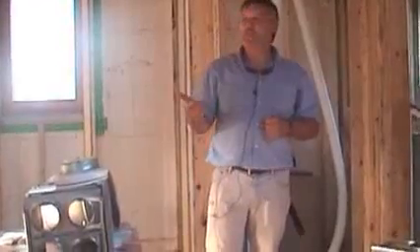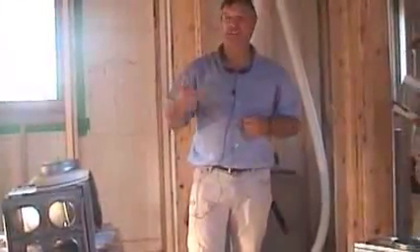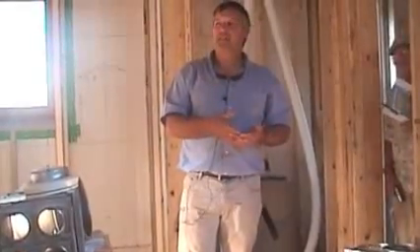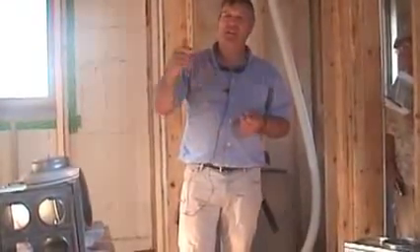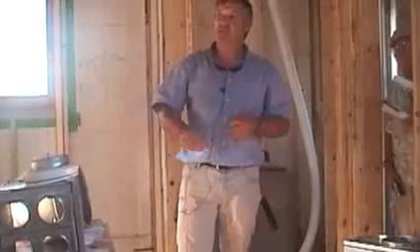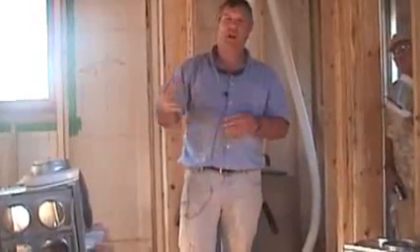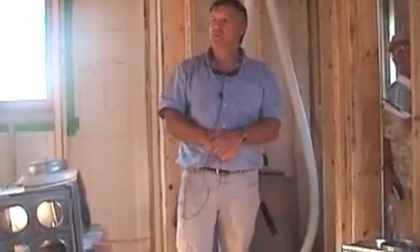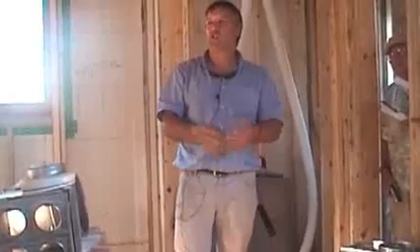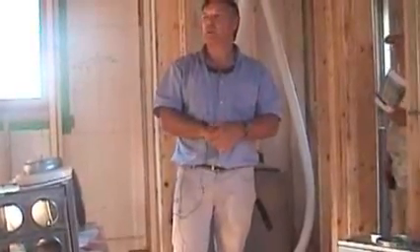So he's getting about 40 to 45 degrees out of the ground loop, and on a minus 50-degree night with 70 degrees inside, he's got 67 degrees coming out on the inside. So he's getting 117 degrees lift, and he's using about 50 watts of power to do it.